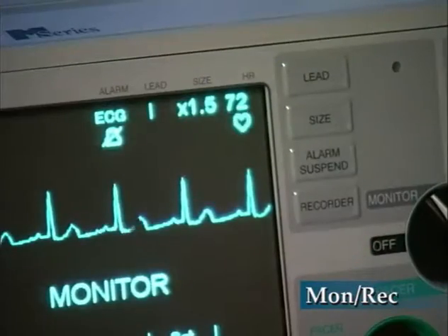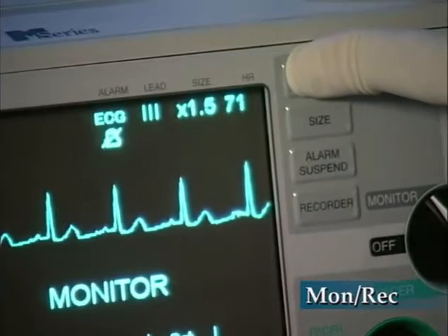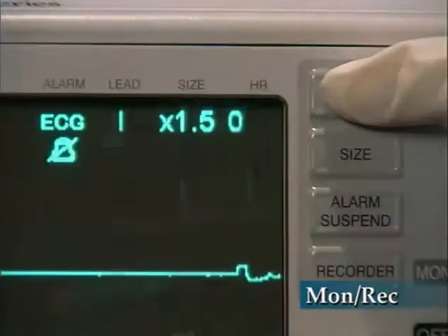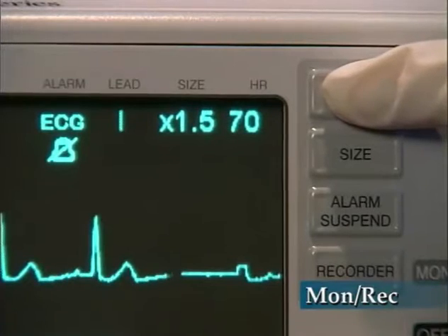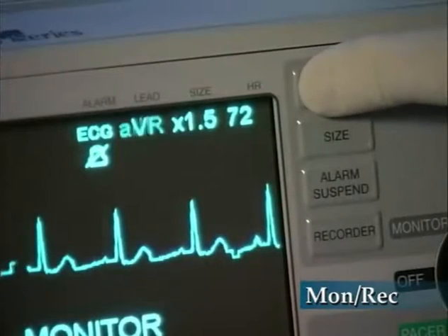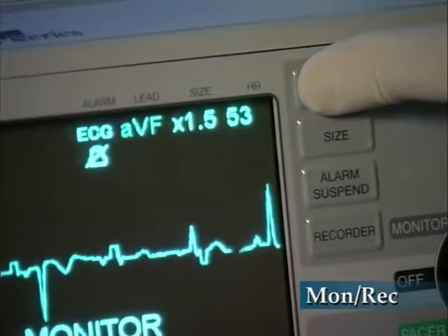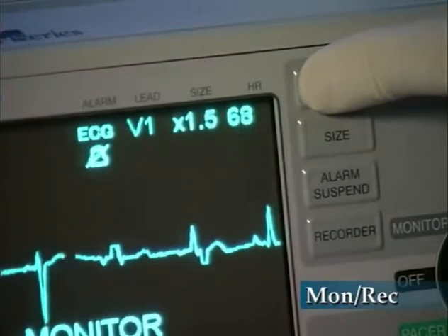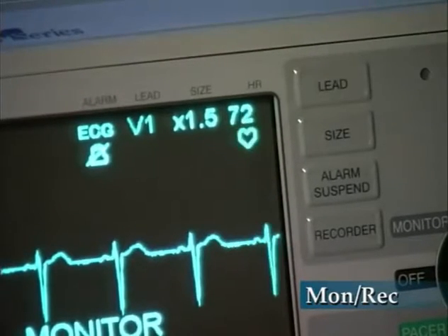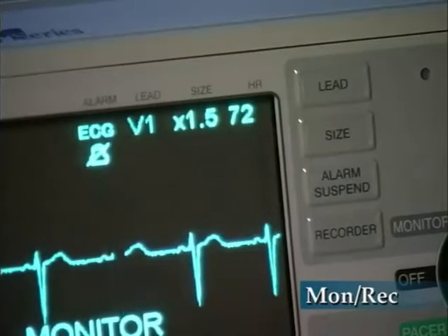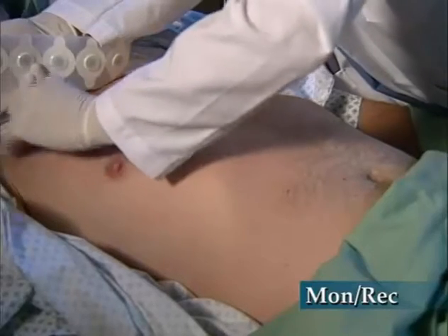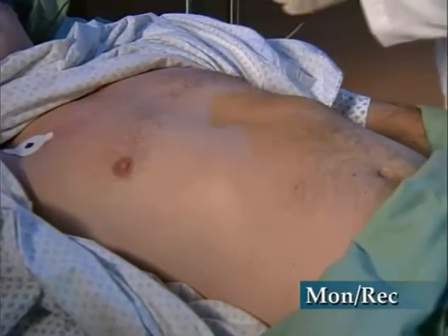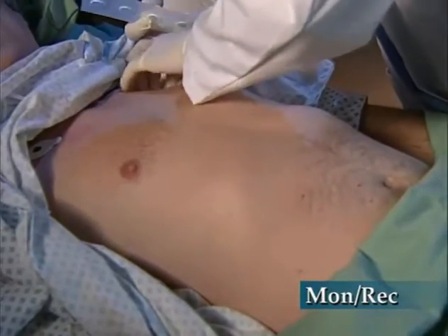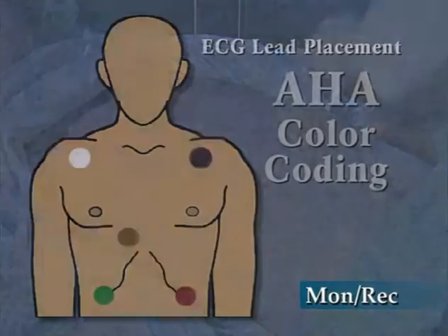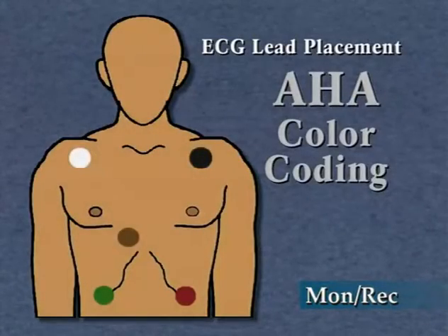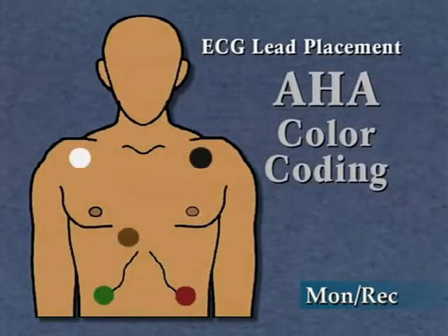When using the 3-lead cable, leads 1, 2, and 3 are available. When using the 5-lead cable, leads 1, 2, 3, AVR, AVL, AVF, and V are available. The lead button automatically adapts to the patient cable selected. Proper application and placement of electrodes are essential for high-quality ECG monitoring. Markings and color codes for the different lead sets are shown in your operator's guide.